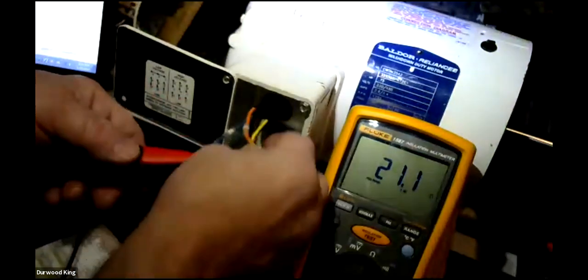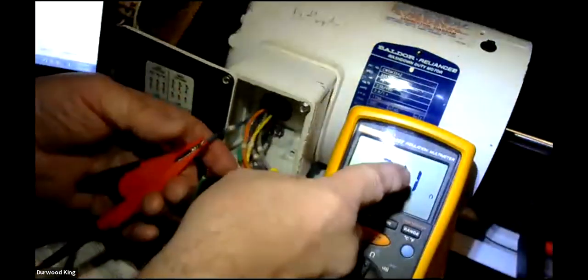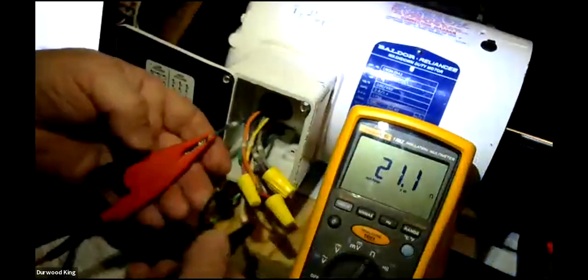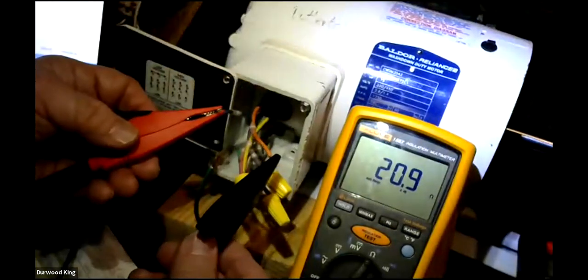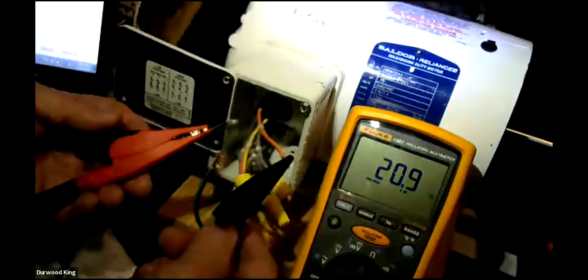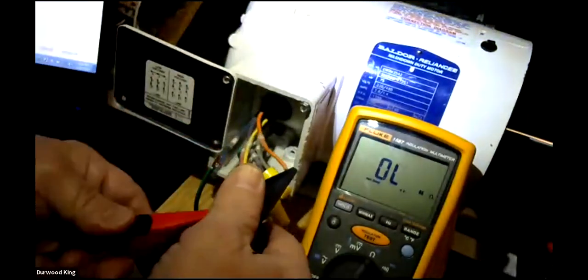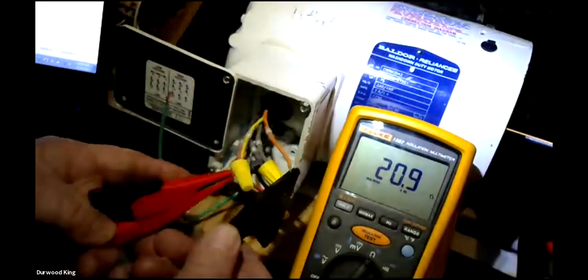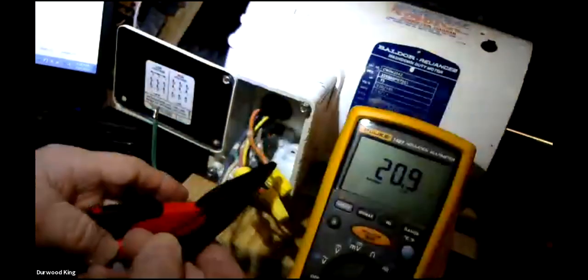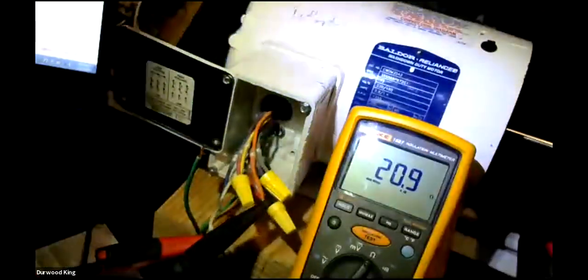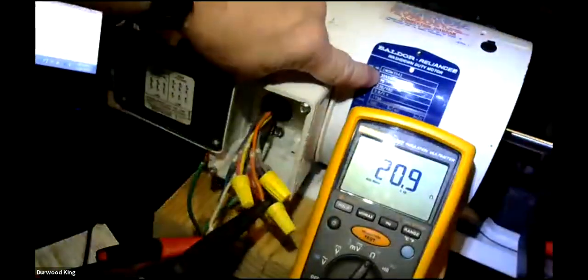So now you went 1 to 2. All right, now let's go 1 to 3. Now keep a note, they all should be close to 21, okay? So that was 1 to 2. Now 1 to 3. 20.9. See that? And now let's go 2 to 3. 20.9. So those windings are what you would consider to be healthy. Those windings are balanced. They're all in the same condition, and that's reasonable for a small motor. That's a 3/4 horse motor there. That's not even a whole horse. It's a 0.75 horse. So that's okay.